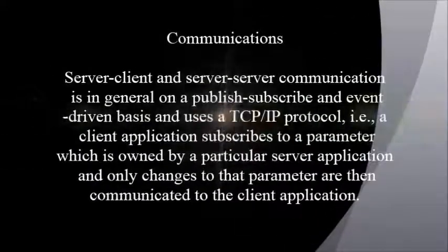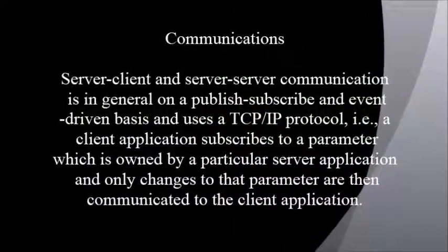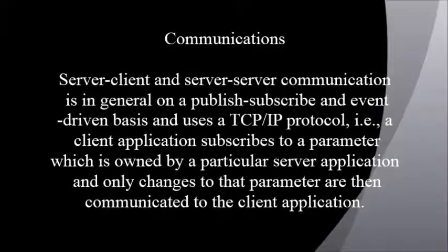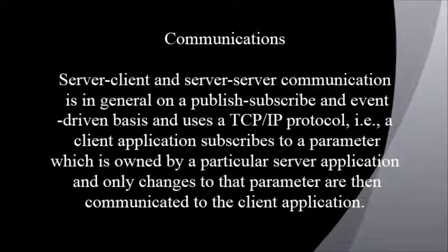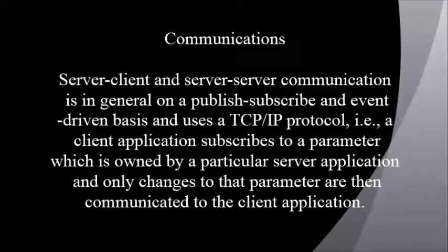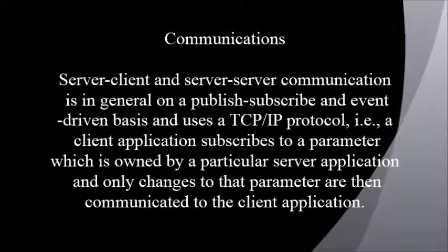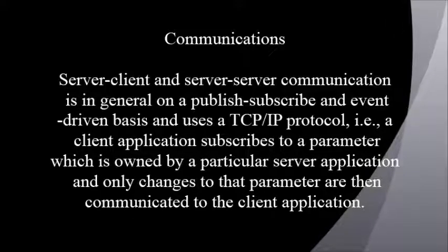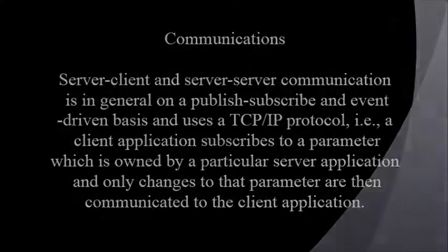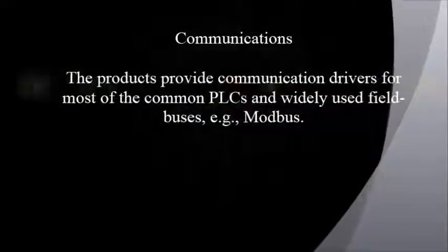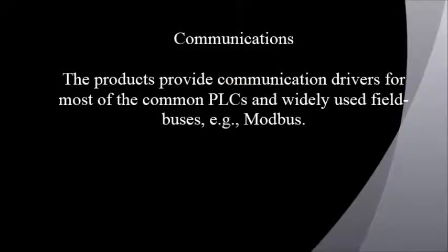Communications. Server-client and server-server communication is in general on a publish-subscribe and event-driven basis and uses a TCP/IP protocol. A client application subscribes to a parameter which is owned by a particular server application, and only changes to that parameter are then communicated to the client application. The products provide communication drivers for most of the common PLCs and widely used field buses, for example Modbus.